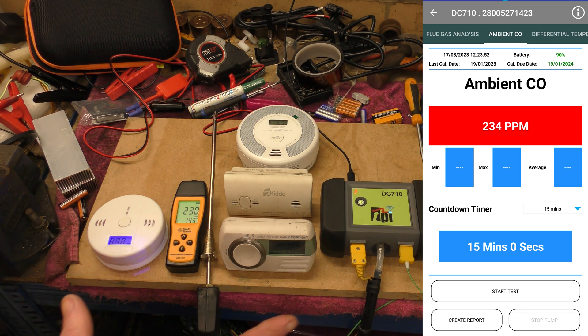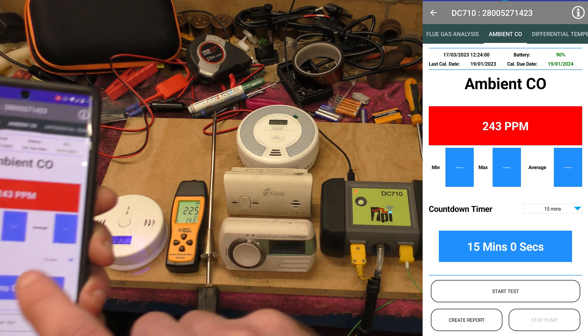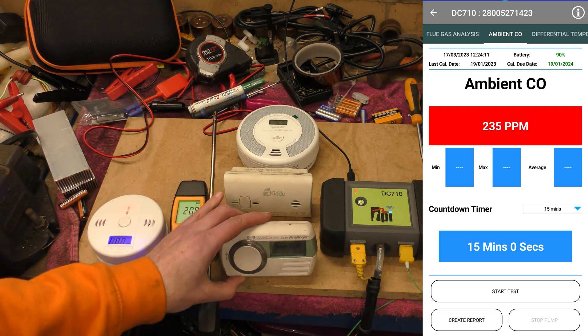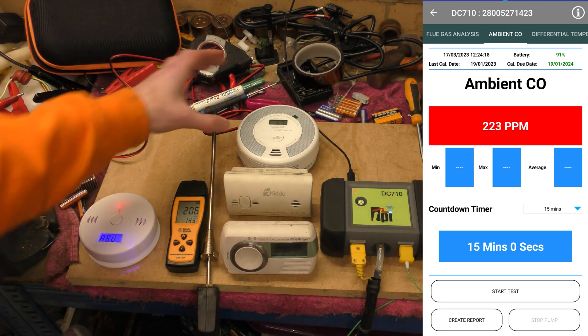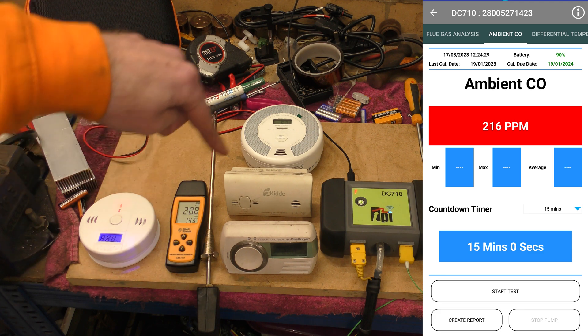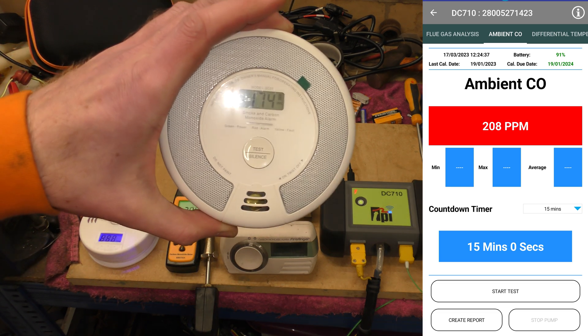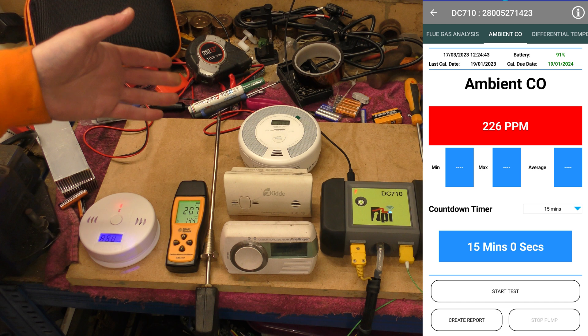Okay, while everybody's beeping in the background at me, let's just do some readings. The TPI is showing 243, 256 ppm. The yellow one is showing 220-odd ppm, the Fire Angel is also showing 220-odd ppm. The cheapest one is showing 190 ppm, and the Xsense is sadly still showing 67 ppm. The Xsense is now at 174 and heading up - now 183 - so it's getting there.